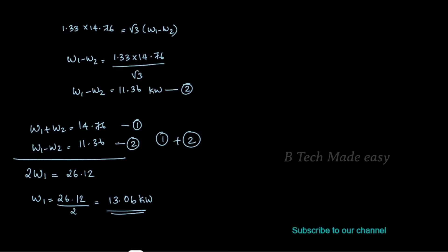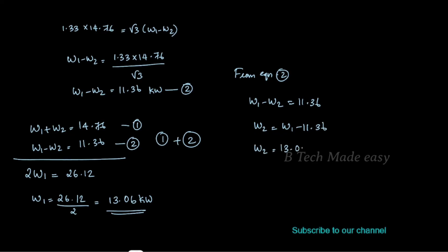From equation 2, W1 minus W2 equals 11.36, so W2 equals W1 minus 11.36, which is 13.06 minus 11.36. Therefore W2 equals 1.699 kW. So the two wattmeter readings are W1 equals 13.06 kW and W2 equals 1.699 kW.